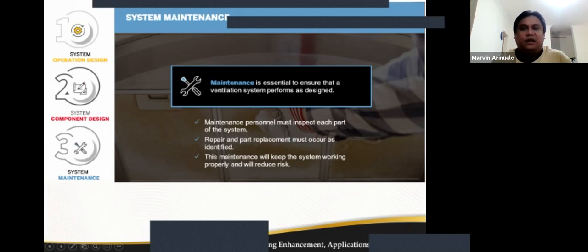And lastly, let us discuss system maintenance. Maintenance is essential to ensure that the ventilation system performs as designed. Both components and the system as a whole must be kept clean and physically and operationally in proper condition. The maintenance or facility personnel must inspect each part of the system and test its performance on a regular basis to catch and correct the first slip from normal operation. Repair and part replacement must occur as identified, and the maintenance will keep the system working properly, which will reduce potential risk.